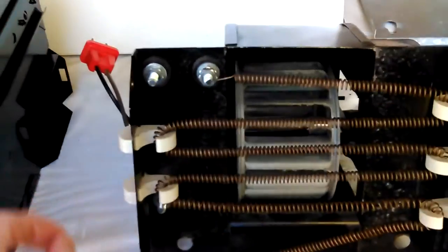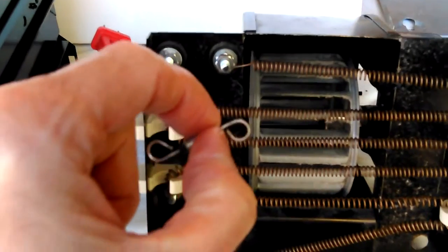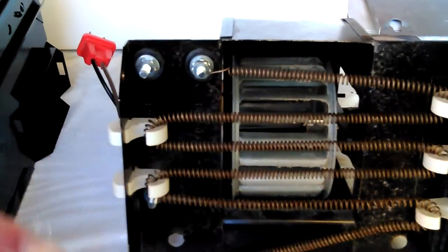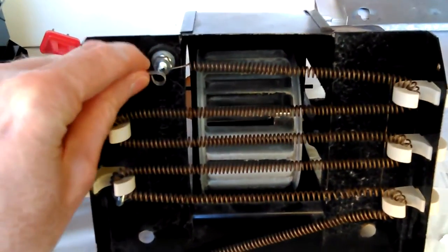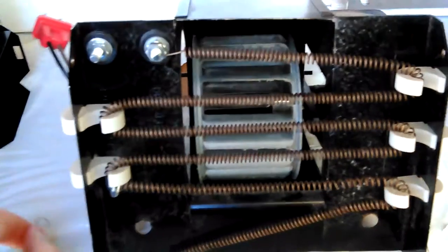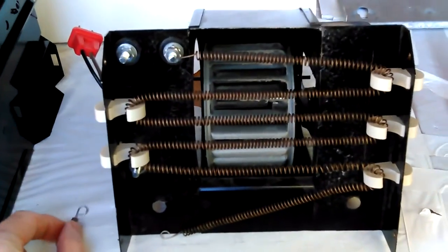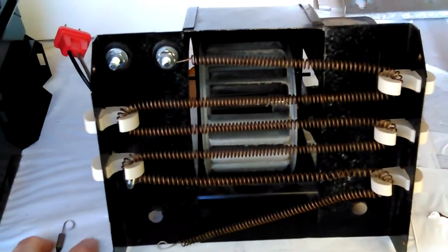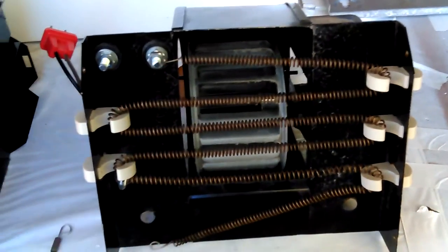Turns out the thermocouple is bad. I figured that out yesterday without even taking it apart. With my multimeter I did a continuity test and there was no conduction between those points. I thought well that's bad.